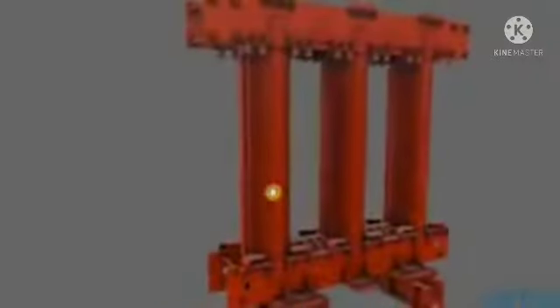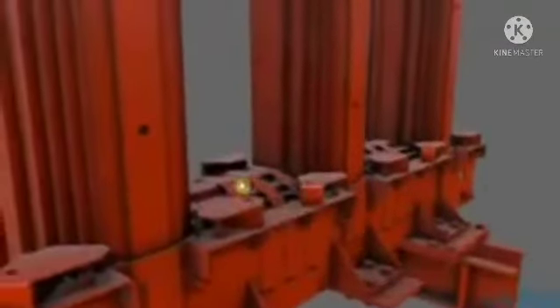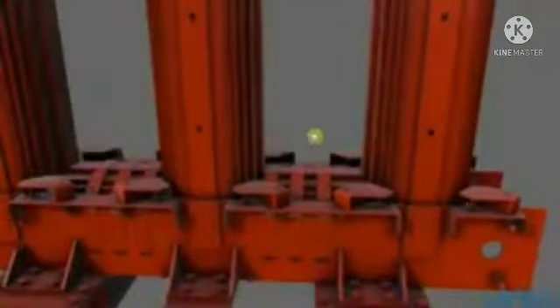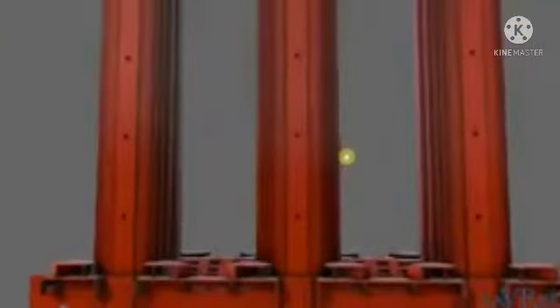The core itself is clamped together, usually using adhesive or some straps. If we look on the bottom here, we can actually see there are 3 straps. It's these items here. And you'll see there's also straps on the other side. 1, 2, 3. So the transformer core is clamped together, and the reason it's clamped together is because the core is not one solid block of metal. It's actually a series of metal sheets that have been clamped together. You'll actually call these laminate steel sheets.